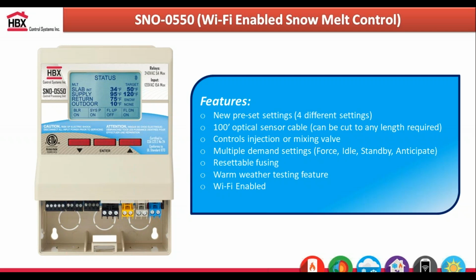There's also a warm weather testing feature on the Snow 550. Most of these jobs are installed in the spring and summer. You can put it into a setting that tricks the controller into thinking it's cold outside, then pour a little bit of water on the optical sensor to simulate a snow melt mode and make sure everything is running fine. After about 30 minutes, it'll go back into warm weather shutdown. This controller also has built-in Wi-Fi capabilities. Simply put it into Wi-Fi settings mode, and it'll connect to whatever Wi-Fi network is available.